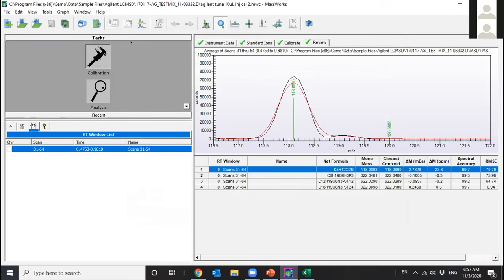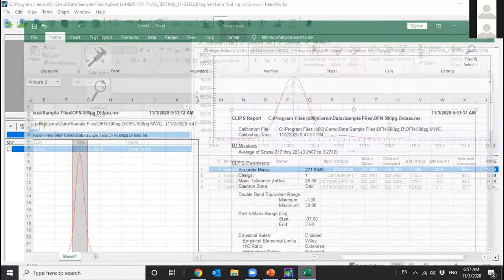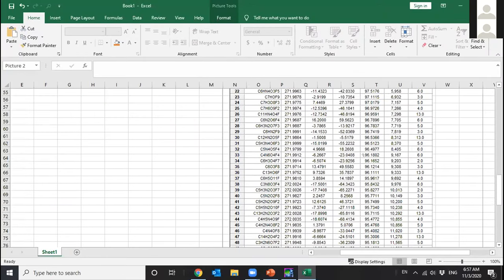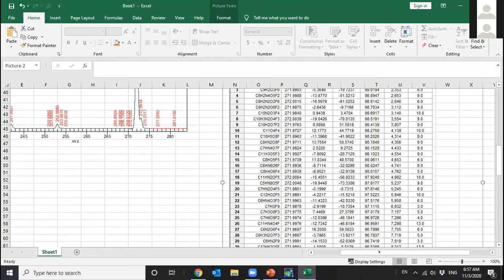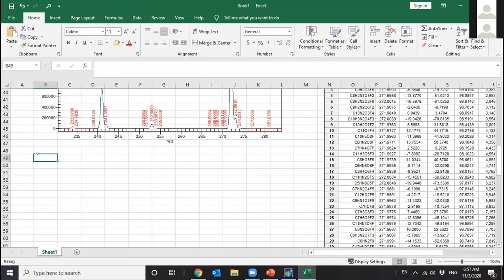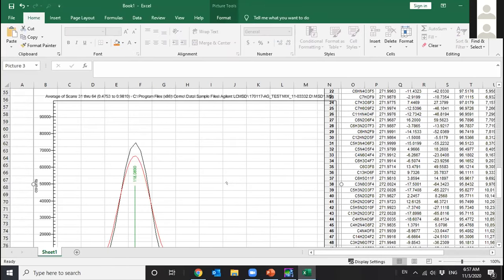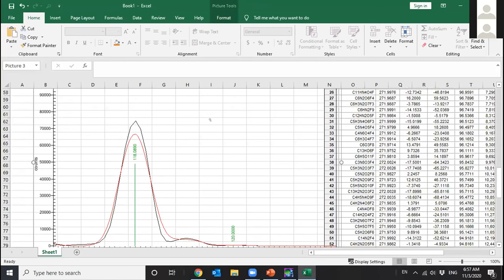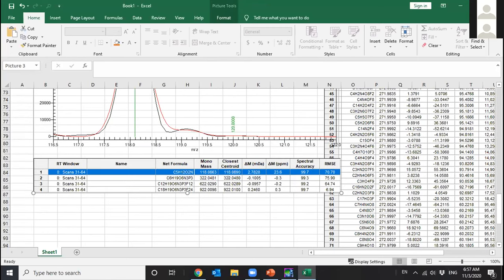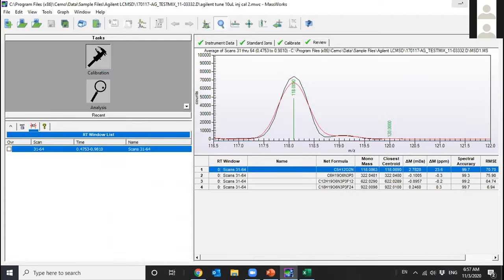And this calibration report, you can also go to edit, under edit, say copy and report to clipboard. You can also copy and paste that as an image file to keep as a record for your own record keeping, as the calibration file that's built today. And it shows under what conditions, which data file, and the mass accuracy and the spectral accuracy. So that's another piece of a one page report that may be useful. And then at the end of that, the calibration is all finished, calibration file saved.